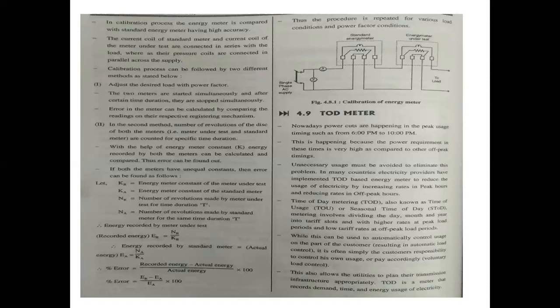If both meters have equal constants, then the error can be found as follows. Kr is the energy meter constant for the meter under test; Ka is the energy meter constant of the standard meter; Nr is the number of revolutions made by the meter under test for time duration T; Na is the number of revolutions made by the standard meter for time duration T. The energy recorded by the meter under test is Er = Nr / Kr, and the energy recorded by the standard meter is Ea = Na / Ka. The percentage error is equal to (Er − Ea) / Ea × 100.